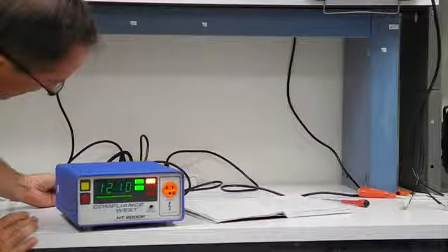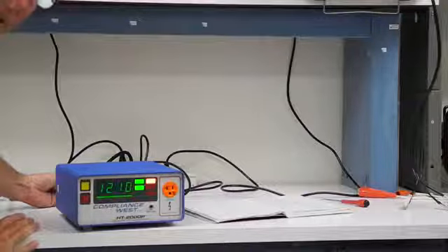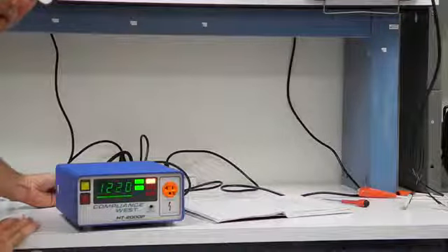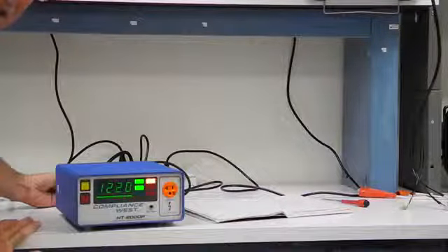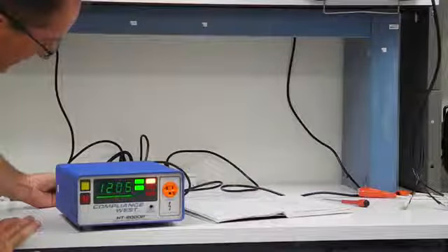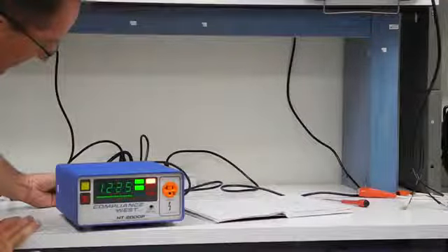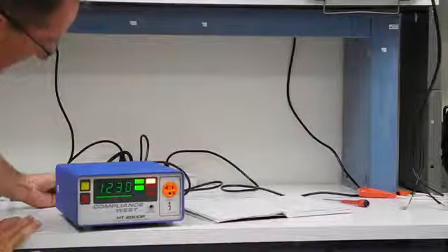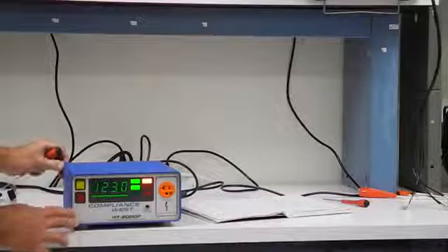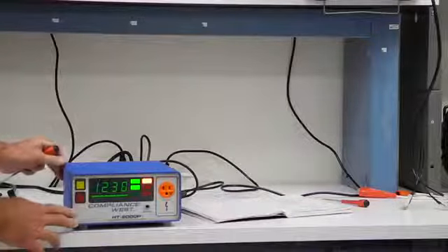It's going to set it for 1200, right? I'm going to go a little bit higher because we're variac controlled, and so line fluctuations will be a factor here. So I always set it maybe just a little bit more. Let's just set it for 1235, 1230. That way, if your line sags a little bit during the day, you'll still be at 1200.